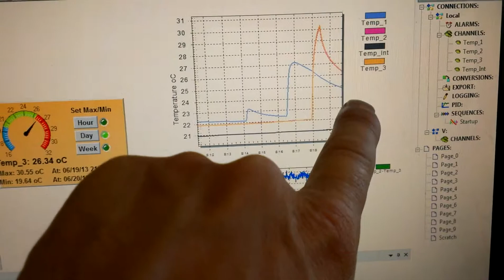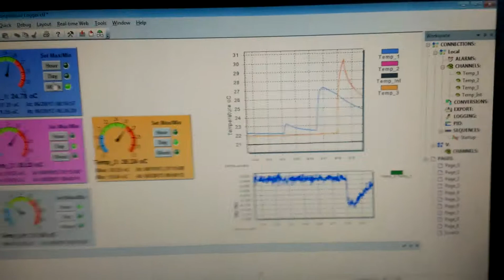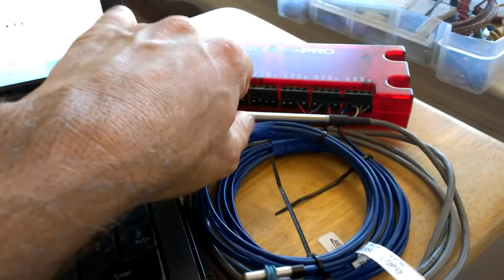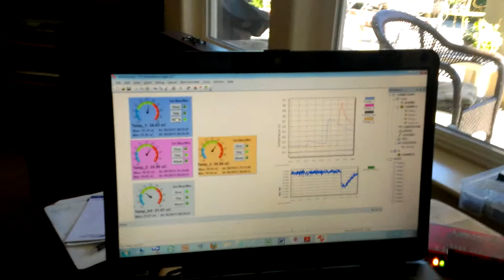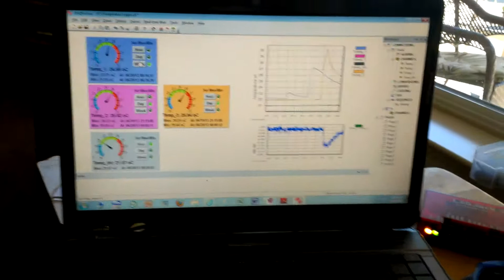You can see as the thermocouples are cooling back down, the rate of change in temperature is going down, and now the sensors are reading almost the same. I've played with two of the silicon temperature sensors at the same time, and they're very consistent to each other in terms of equilibrium temperature readings, but they do have a different response rate. My guess is it's due to how the sensor is mounted in the end of the tube. These thermocouples are grounded thermocouples, so the actual thermocouple junction is touching the metal sleeve, so they have really fast response. And I'm reading them as single-ended inputs, so you may be able to get better results with differential inputs, but this seems to be working really well. And anyway, that's my temperature monitor.